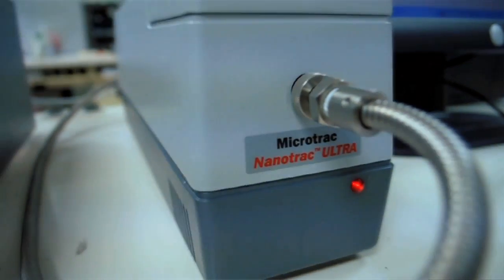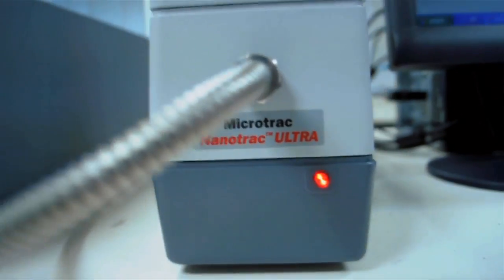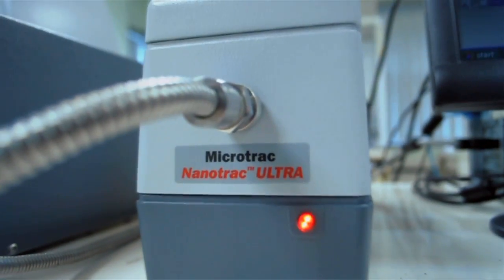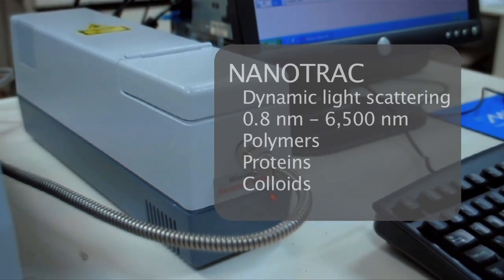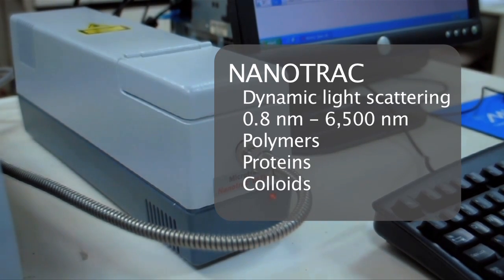I would like to introduce the Nanotrac, which is a particle size analyzer from the brand Microtrac. The Nanotrac is based on dynamic light scattering technology and allows the user to determine the particle size distribution of nanoparticles such as polymers, proteins, and colloidal suspensions.